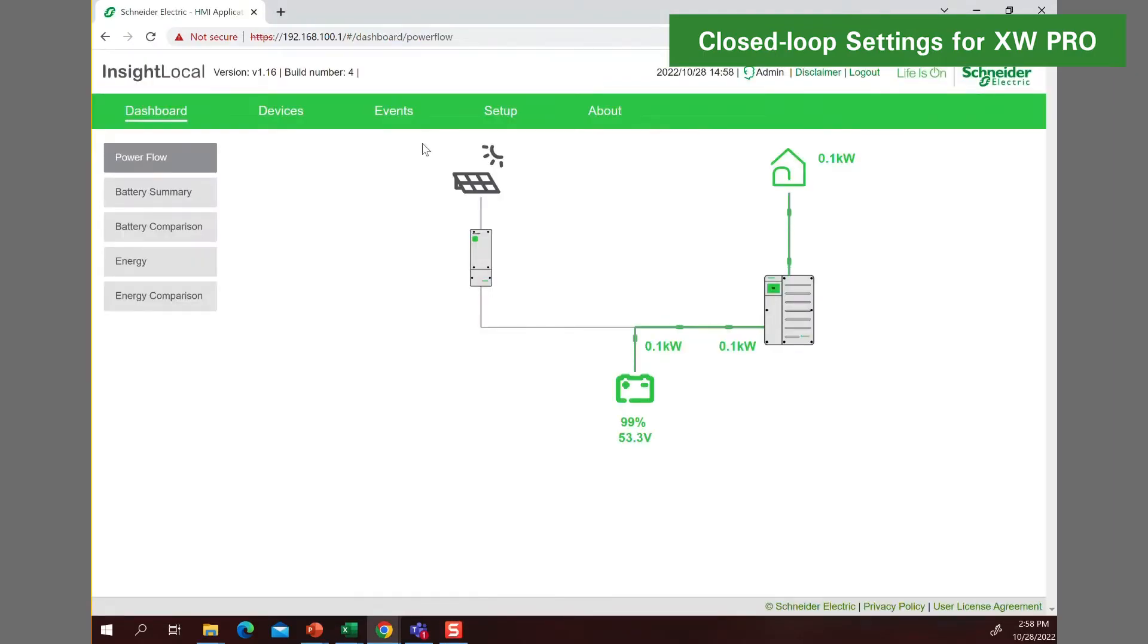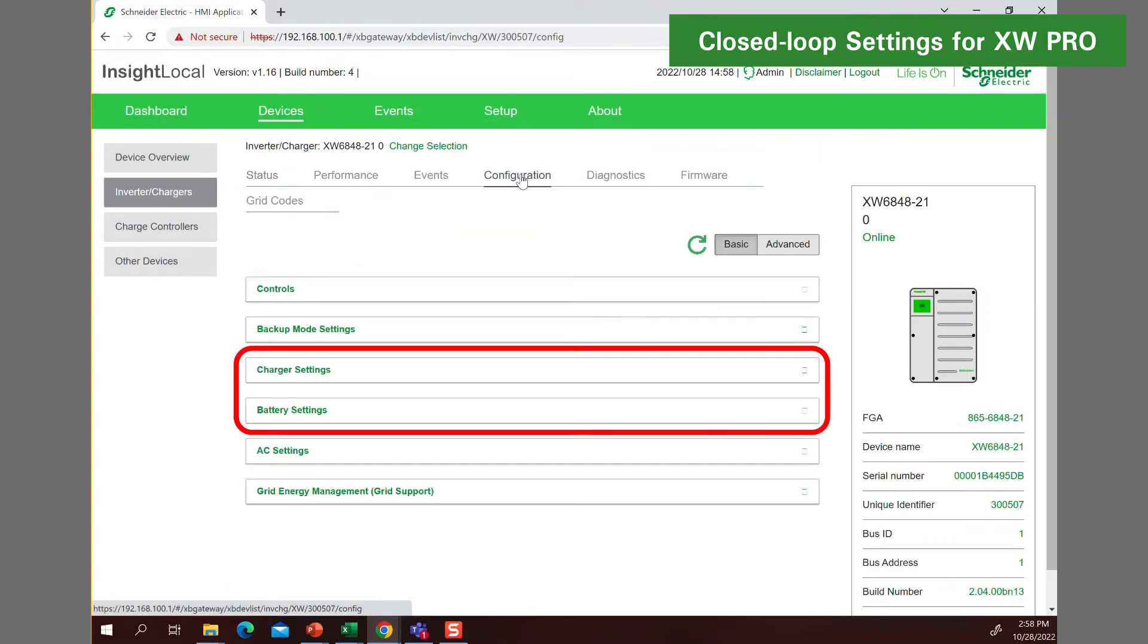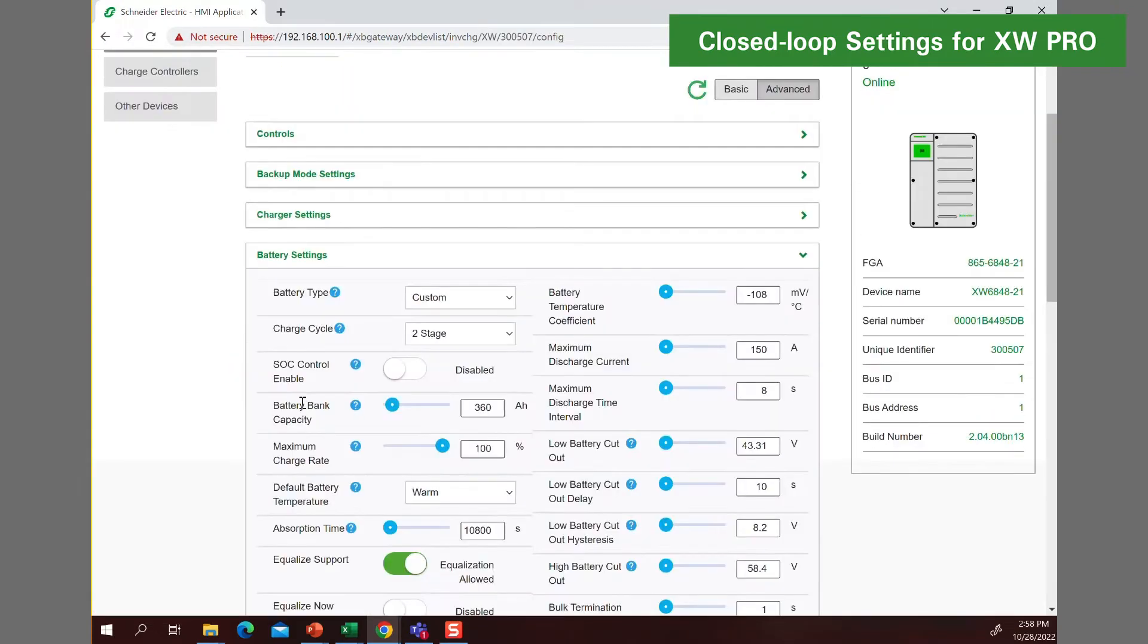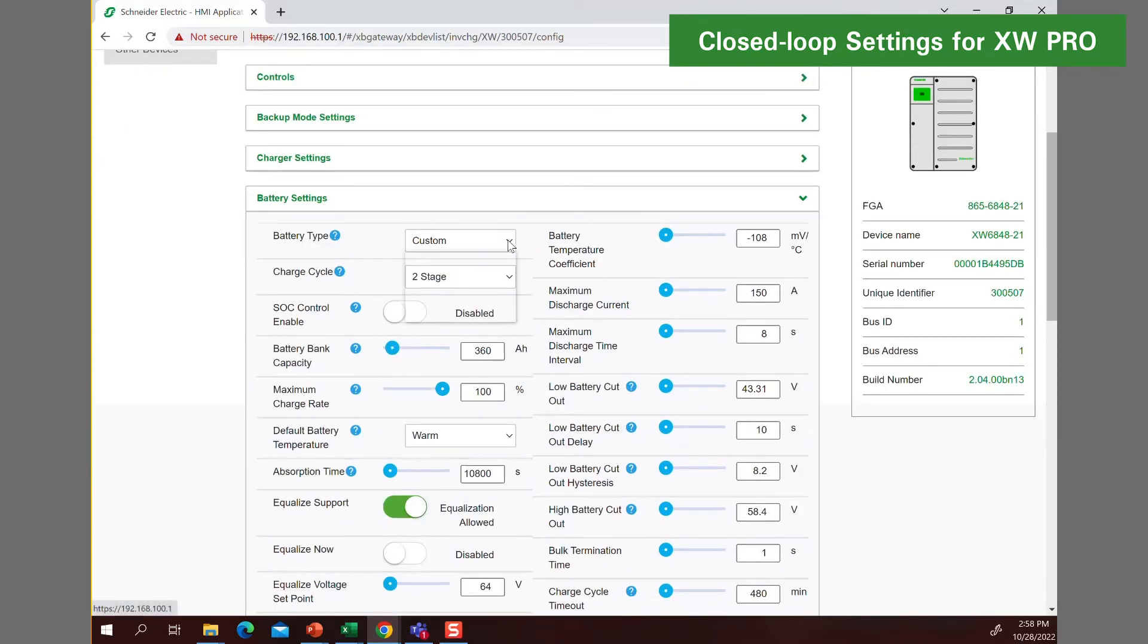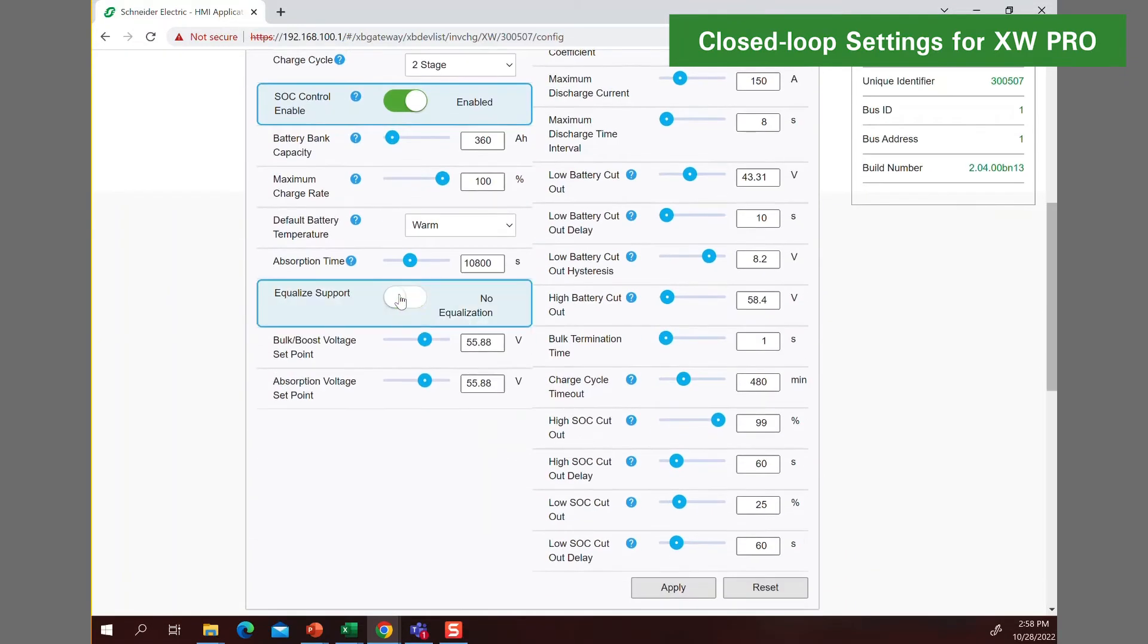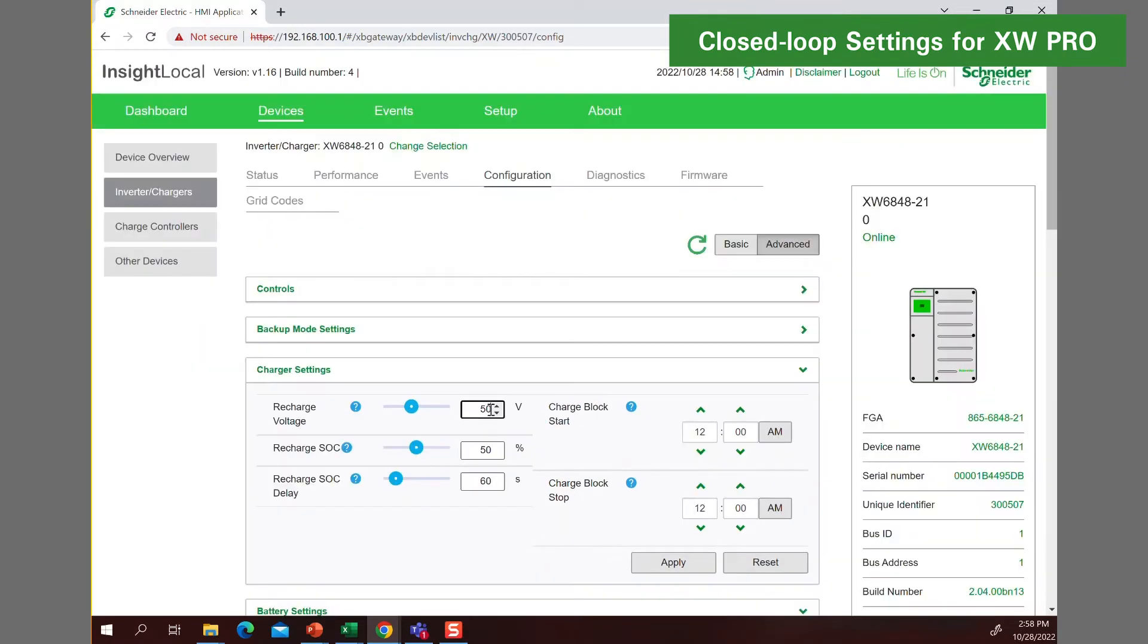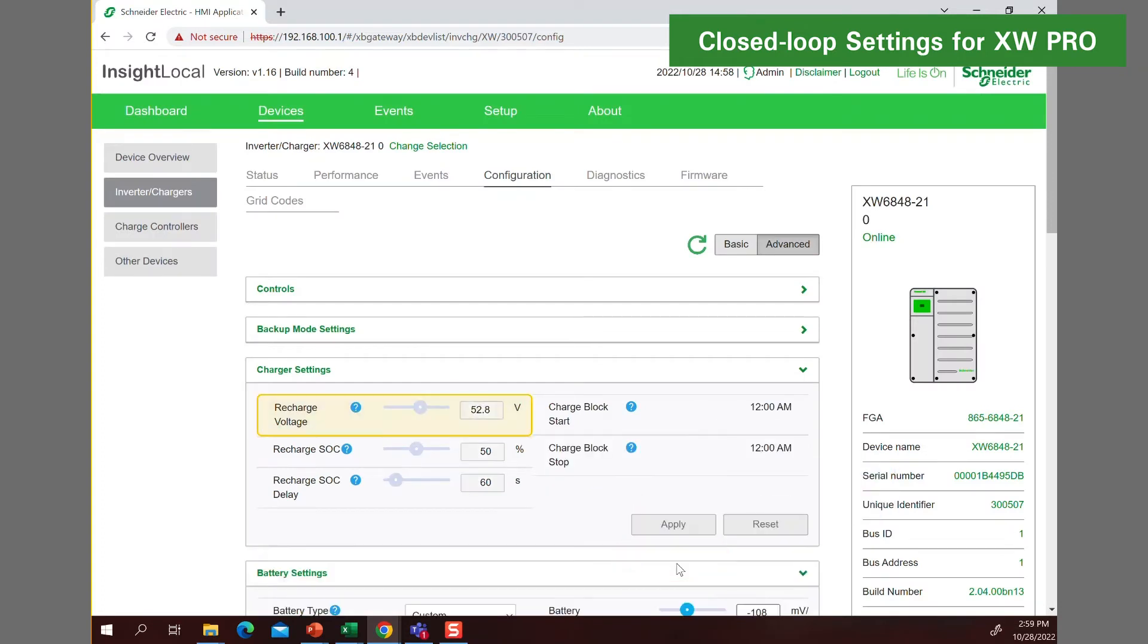Many battery settings and charger settings are automatically populated and cannot be changed. These settings are referred to as fixed and dynamic settings. The Discover lithium battery will automatically reprogram them if they are changed. Some settings are user adjustable and help manage the operation of the XW Pro to match user preferences. Settings on Insight Local are saved by clicking on the apply button. Confirm all settings have been accepted by refreshing the Insight Local menu screen.